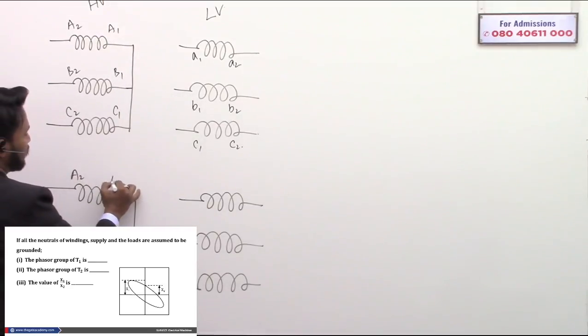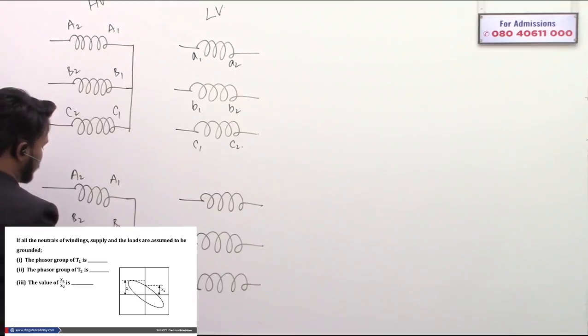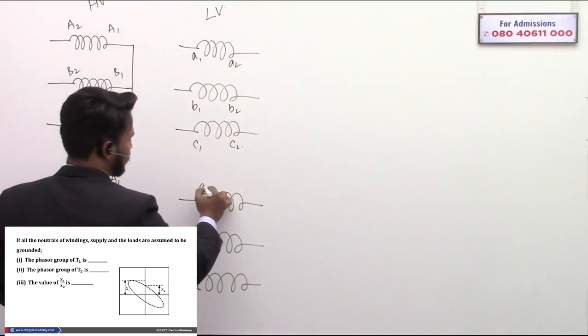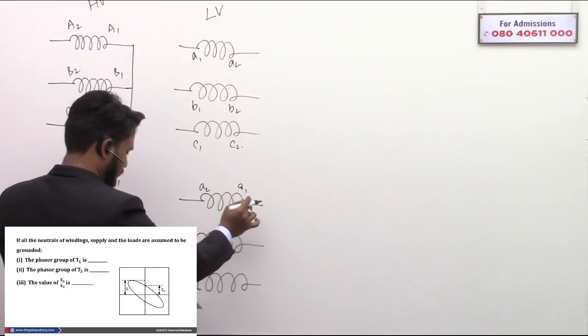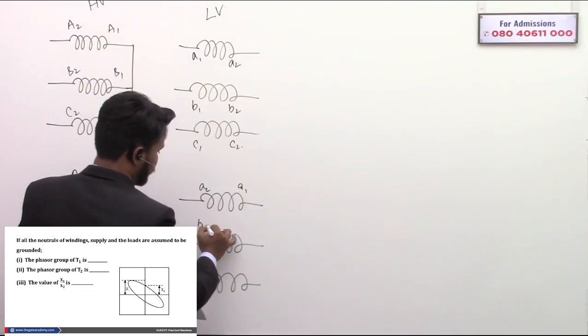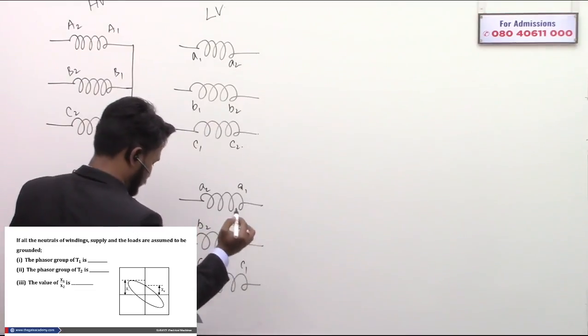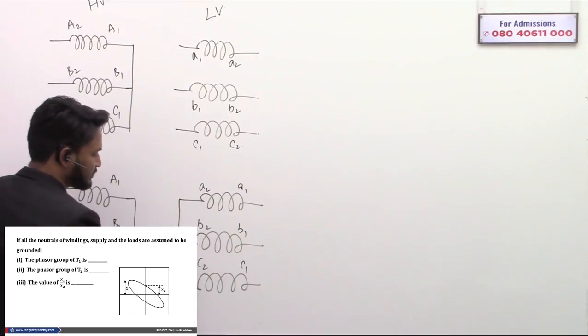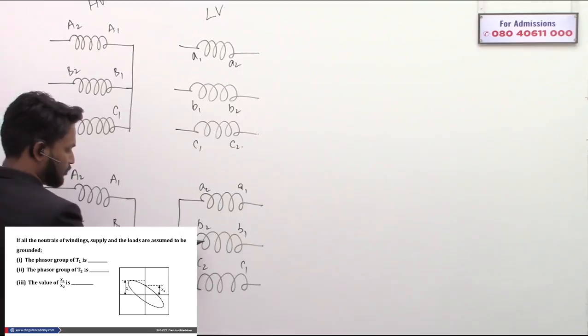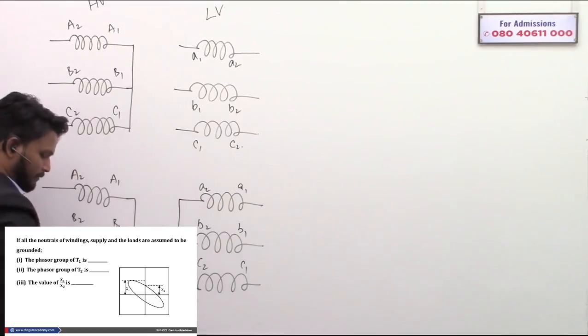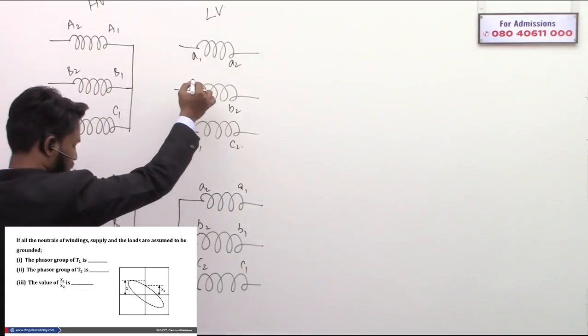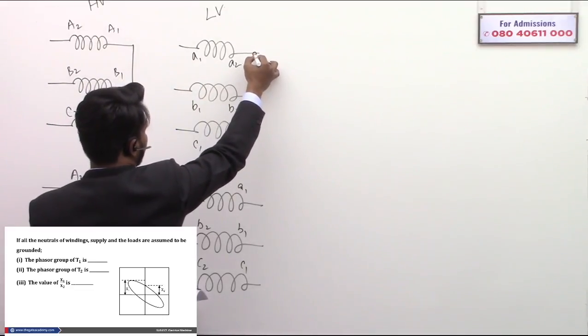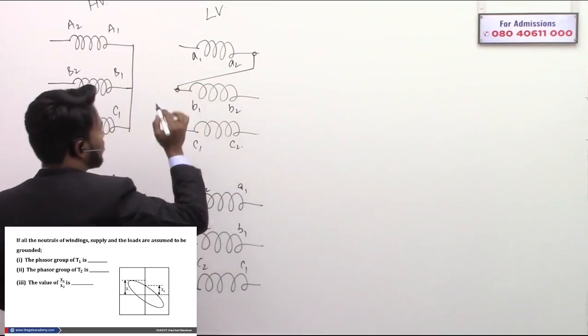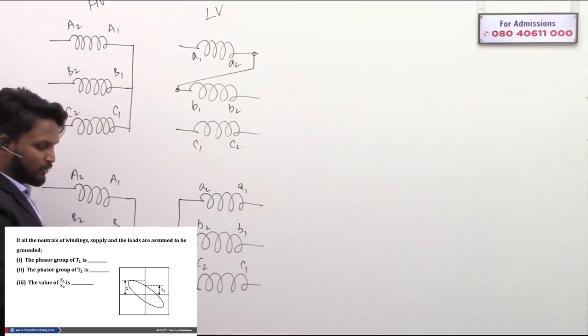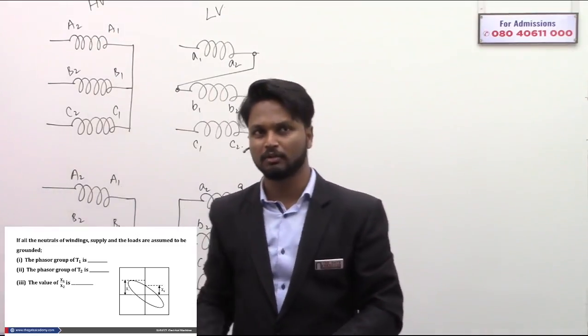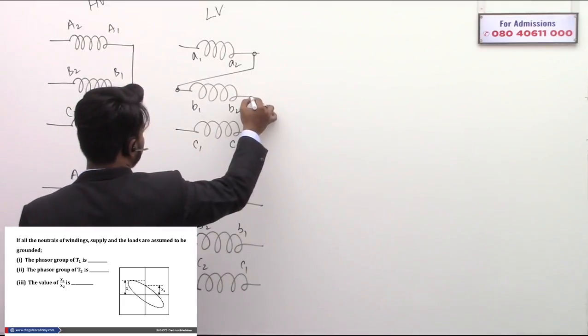Again here: a2, a1, b2, b1, c2, c1. These three are shorted, and this terminal is called neutral. Neutral of LV should be indicated with small n. On the other hand, on this particular winding you do not have any neutral — in a delta winding, you don't have any neutral.